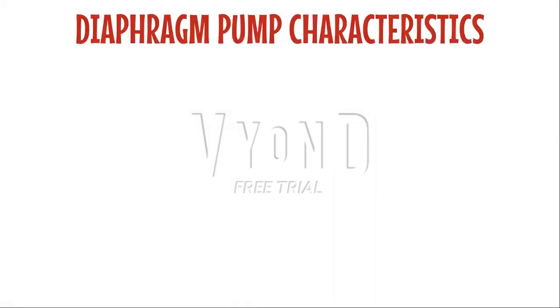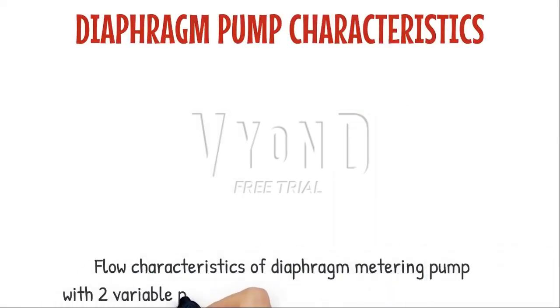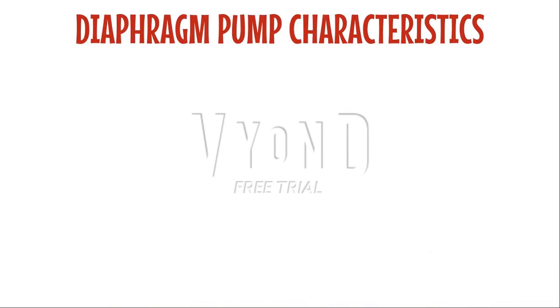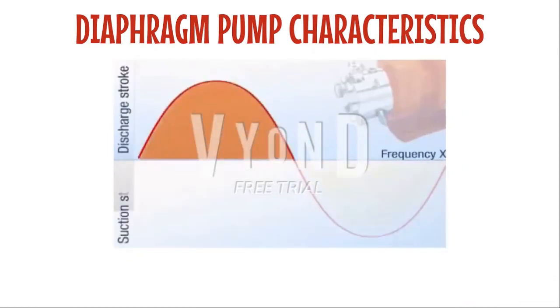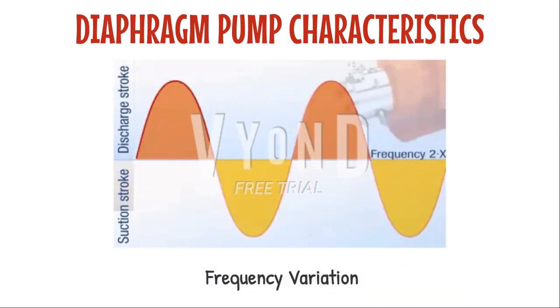The pump's flow can be controlled by adjusting the motor's rotation speed or pump stroke. Pumps using a diaphragm metering system deliver precise quantities each stroke. The flow is variable; when the diaphragm is on the downstroke and the motor is run at very low rates to achieve small volumes, there is no flow, and long stretches go by without any liquid being supplied.